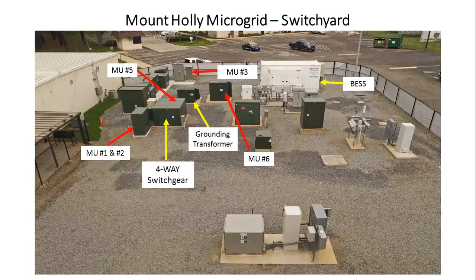So this is the yard that we were talking about, right? In order to do 61850, you probably know that you need communications, you need merging units in the field, and you need relays at the back. So every single piece that you see here in terms of normal protection and control has its own associated merging unit operating in parallel. The 4-way switchgear has 2 merging units protecting it, MU1 and 2. The grounding transformer has another merging unit, number 3. On the transformer, we put differential protection, so merging units 5 and 6 protect it.